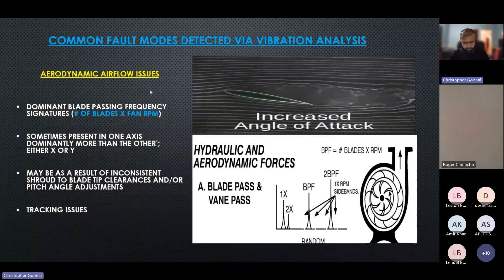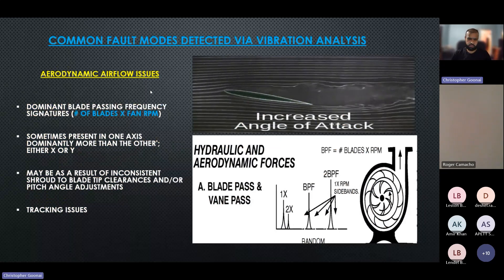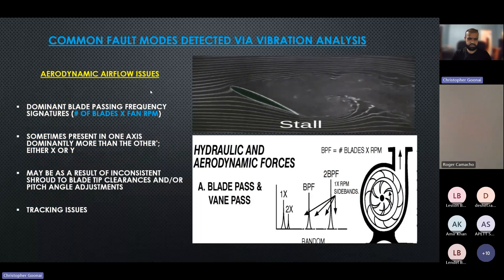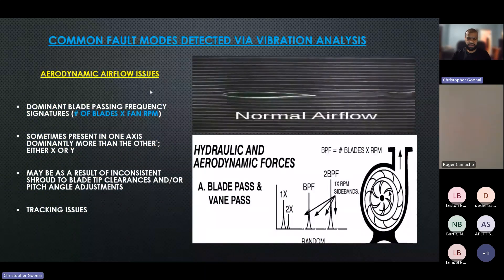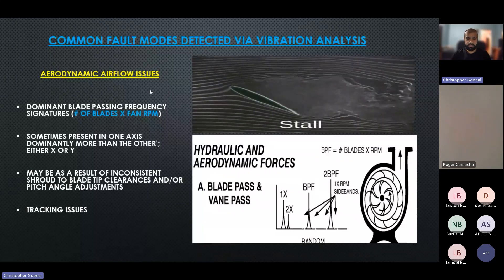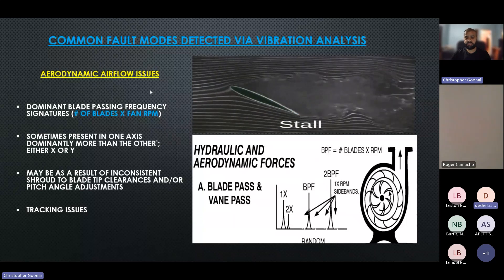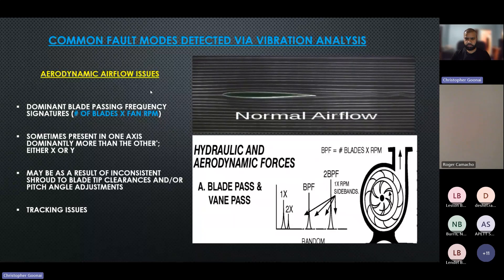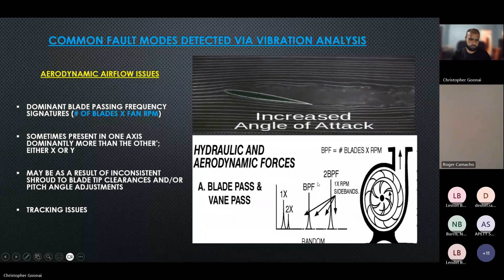Aerodynamic airflow issues — concerning blade tip clearance and pitch angle adjustments — produce a dominant blade passing frequency, which is the number of blades multiplied by the fan RPM. Sometimes it is present dominantly in one axis more than the other — either X or Y — as a result of inconsistent blade tip clearance, pitch angle adjustment, or tracking issues causing flow disruptions. This example shows the X probe with a dominant blade passing frequency at 5X, while the Y probe shows very little, confirming it is predominantly in one axis.